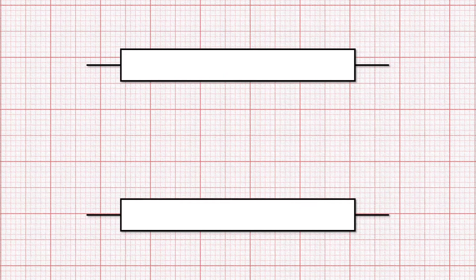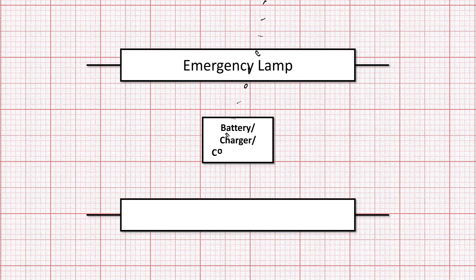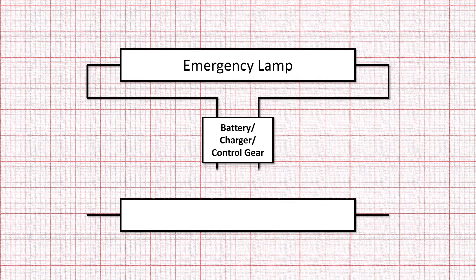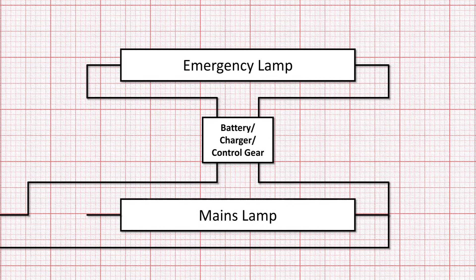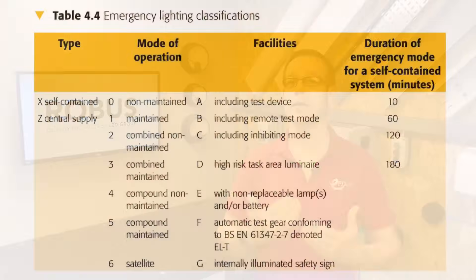These two base modes of operation are then repeated with other types of emergency lighting. Those of us who are a bit longer in the tooth may remember another type called sustained — where an emergency light fitting would contain two or more lamps. At least one was connected to the backup supply and would illuminate when the power died; the remaining lamp or lamps were connected to a switched line conductor. This method still exists, but you won't find the term 'sustained' anywhere in BS5266-1. It is correctly referred to as combined.